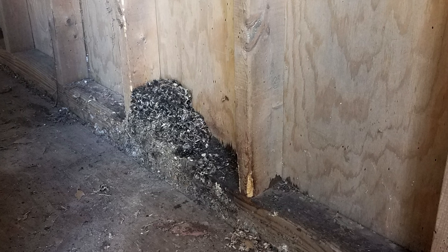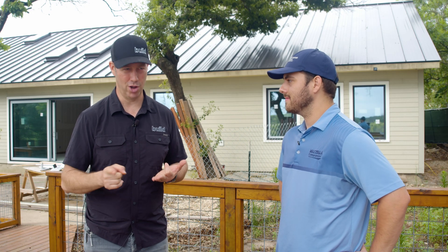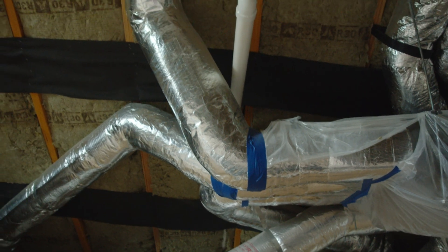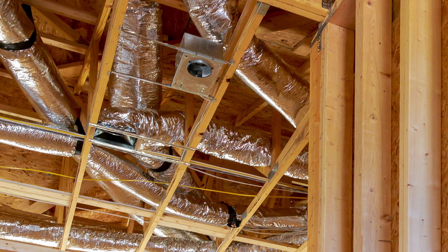I've had raccoons in my attic before I switched to an unvented attic. I had a lemur in my attic, I've had a snake in my attic. Most people's duct work is in their attic when it's 150 degrees on a typical summer day, and you've got little R6 duct keeping your 50-degree air from your 150-degree air. So for many, many reasons — from an energy efficiency perspective, from a healthy house perspective — vented attics are dumb.